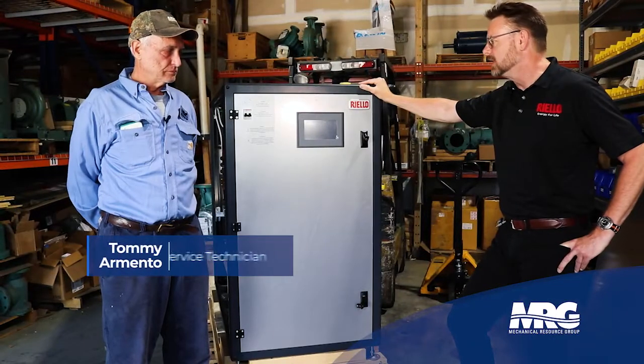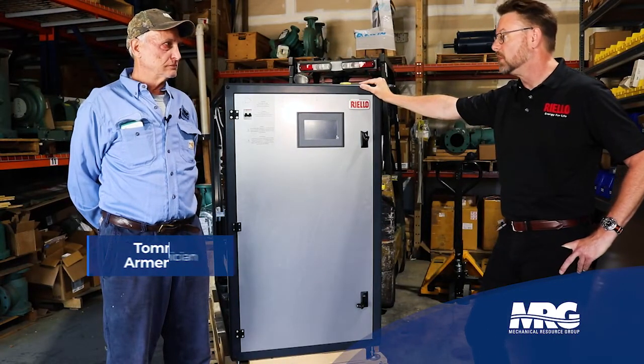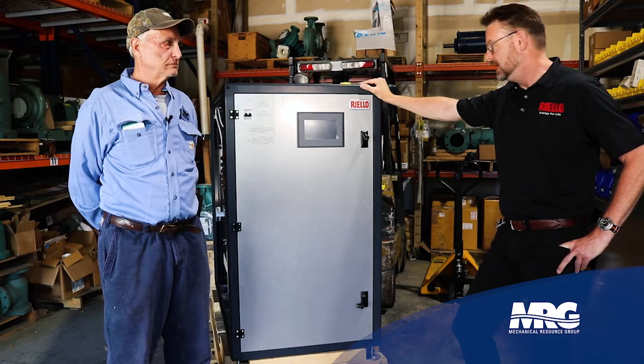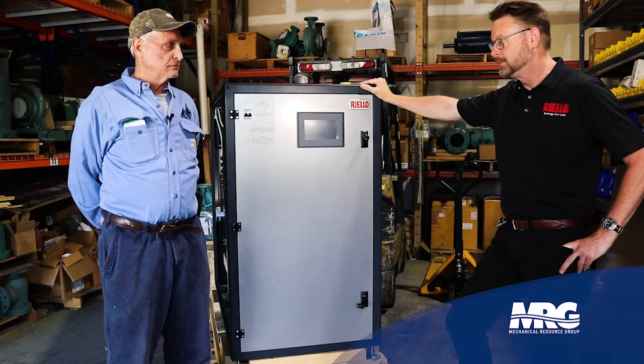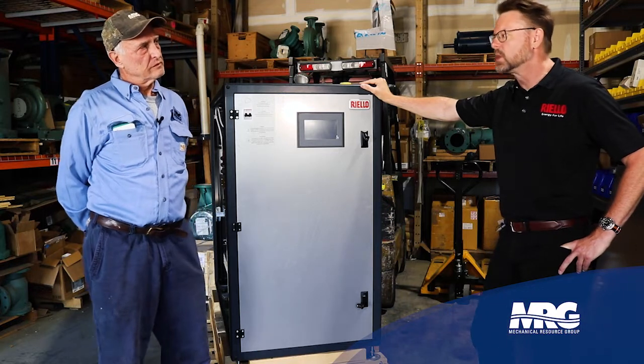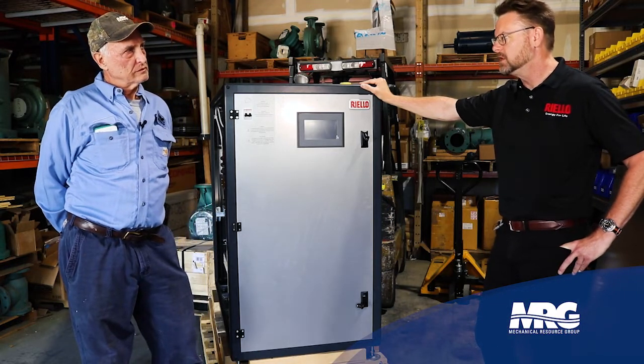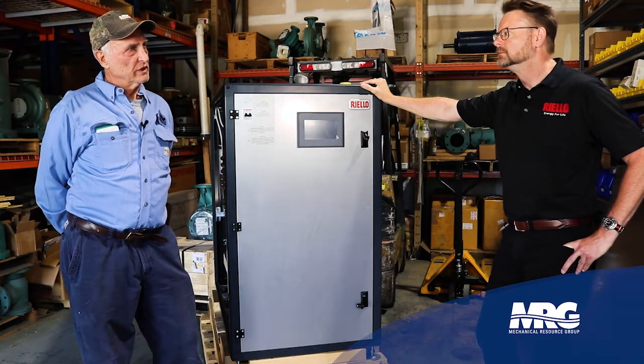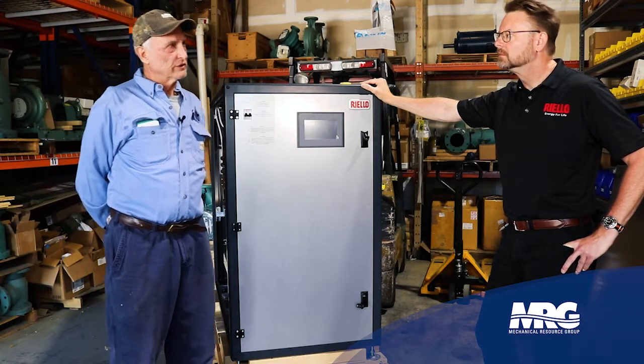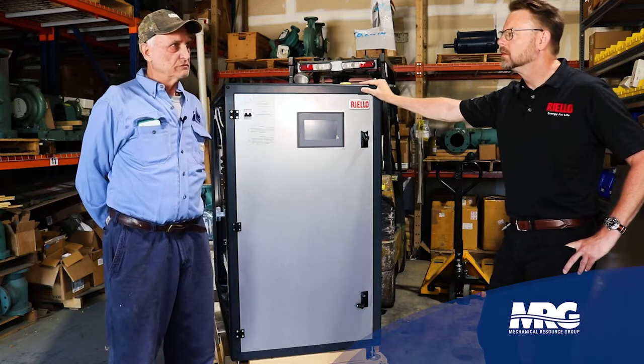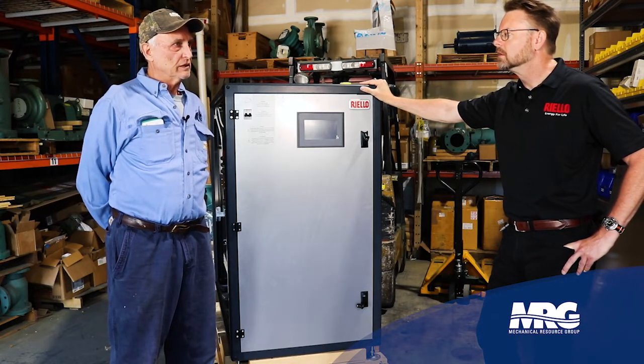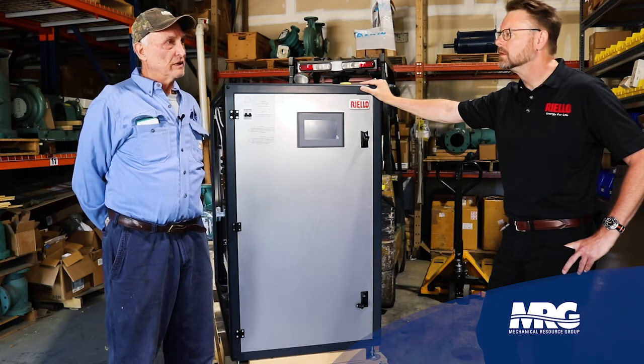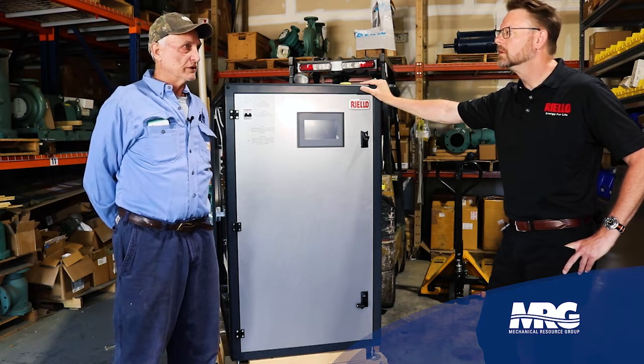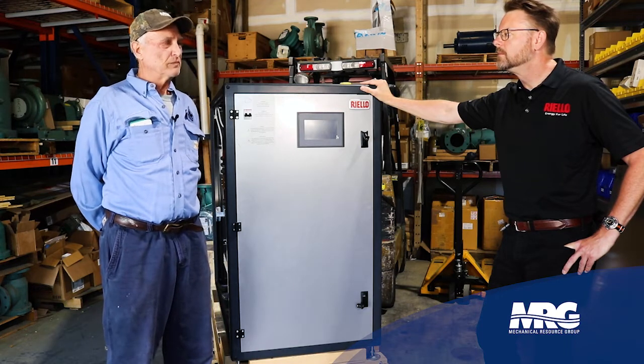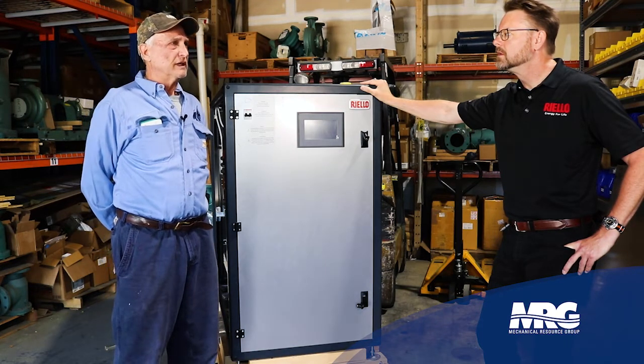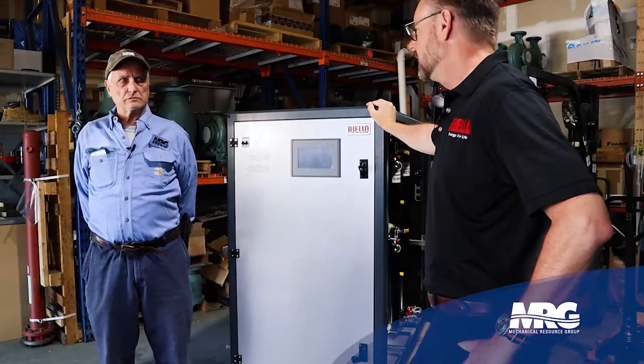What we're going to do is talk a little bit about the wheel of failure and some boiler failures that you've encountered on your calls and how they would have affected the Riello Array. If you could, what are some of the recent boiler failures that you've encountered when you've been called to work on a boiler? Last one was a low water cutoff failure. The boiler was probably 2 million BTU, and it was a 15-to-1 turndown, but they couldn't figure out what was going on, and it turned out that there's a couple of models like this. They use one element to get rid of air. Low water cutoff challenge. Yes.